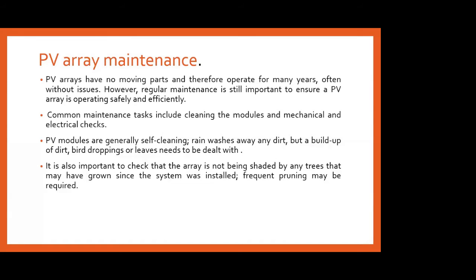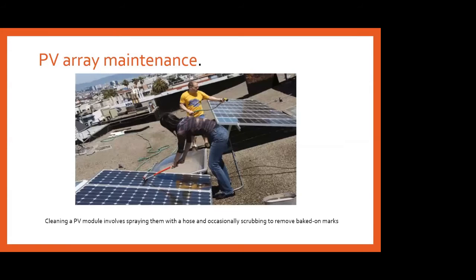The maintenance undertaken by a qualified PV technician will normally include an inspection of the complete mounting structures for any sign of corrosion or mechanical failure, and any attachment to the roof should be inspected to ensure it is still watertight. This is a simple figure shown here: the customer themselves cleaning their PV arrays with water and a small scrubbing brush, to remove any markings on the solar PV arrays.